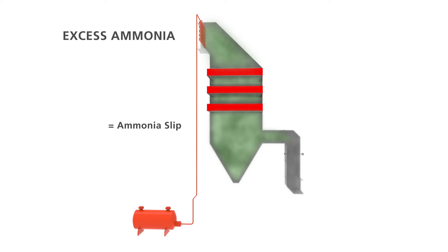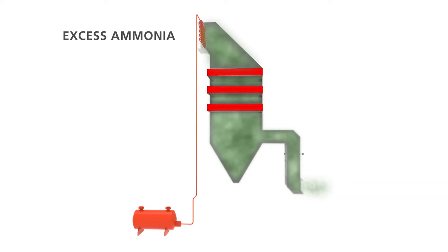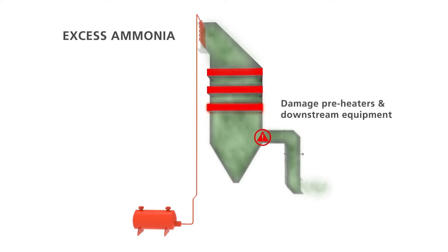Excess ammonia can contaminate the flue gas, becoming an environmentally harmful emission. It can cause acidic ammonium bisulfate to build up, which reduces the operational life of the NOx reduction catalyst. It can damage the preheaters and downstream equipment, increasing maintenance and decreasing efficiency, and contaminate the fly ash, reducing its value.